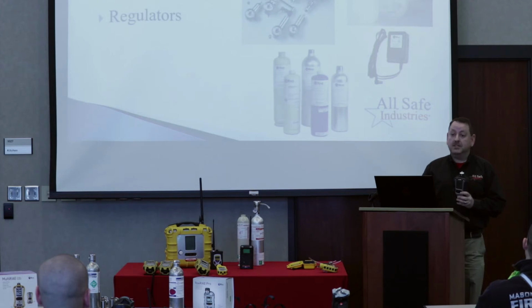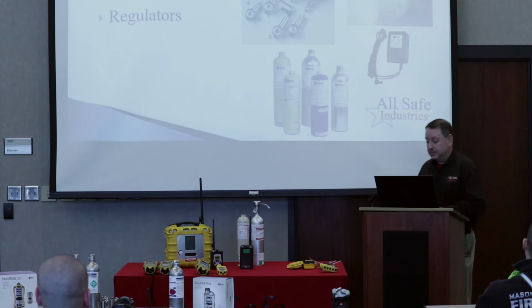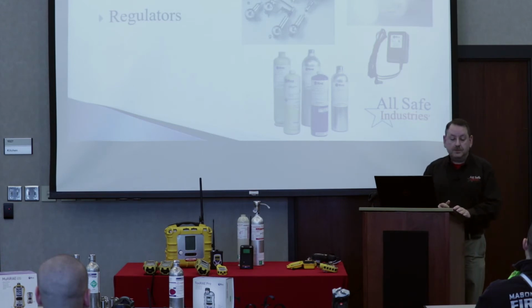That way, if you were to lower tubing all the way to the bottom of a confined space and start to suck up any liquids, the hydrophobic filter will stop it to a point. But as soon as you start seeing liquids coming, go ahead and get that tubing out of the space and off the instrument. More importantly, there are circuit boards in here, and circuit boards don't like to get wet, so make sure you're not ingesting any liquids into the instrument. So you always want to make sure you are using a good filter on your pumped instruments.